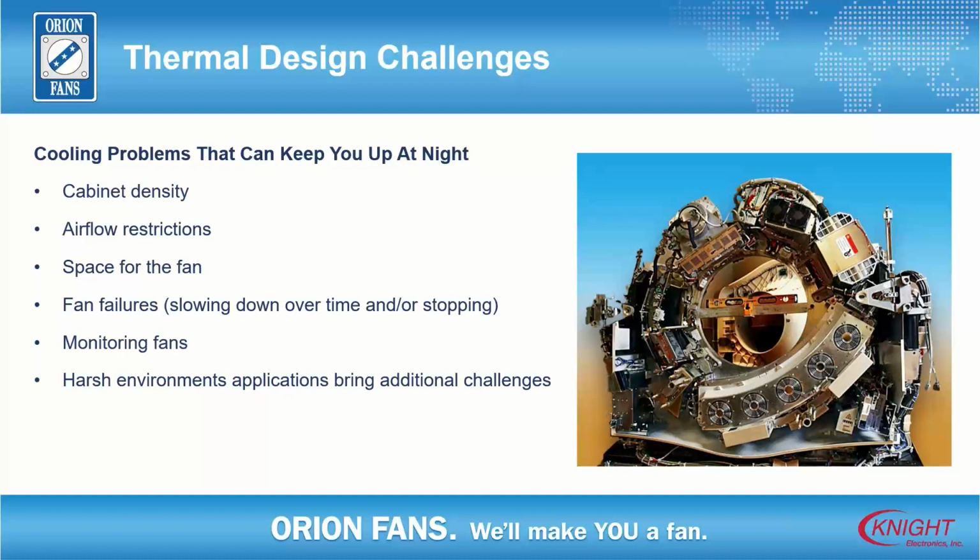The rule of thumb we use is that you should have at least the diameter of the fan away from the fan open, because there's a great big hole in the air where the impeller sits. Heat's the enemy. Heat's the enemy of the electronics. Heat's the enemy of the fan. Fans do not cool things. Fans move air. That's all they do. They cannot cool anything. All they can do is move ambient air.